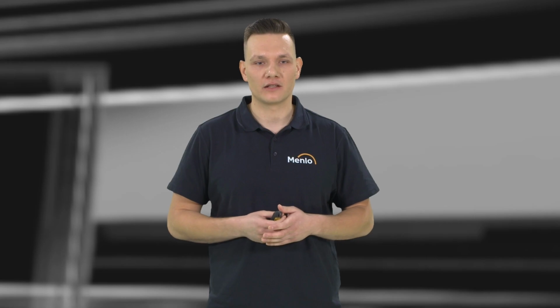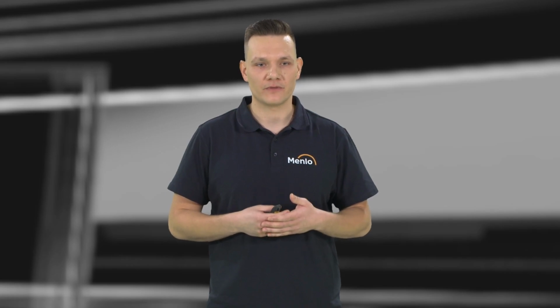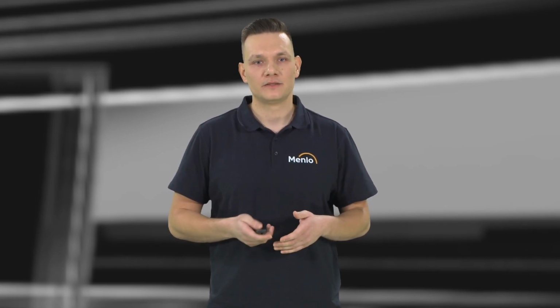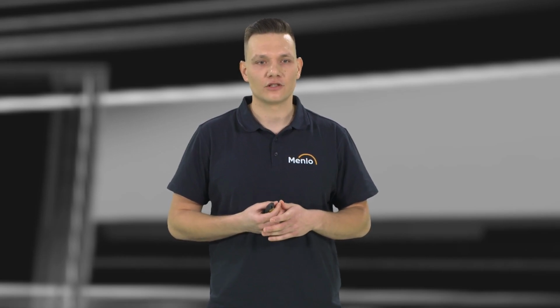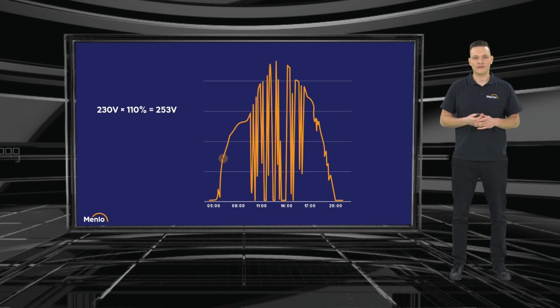Another problem we encounter is high voltage in the grid, in countries where there's too much energy and the voltage goes too high. Because of the network code, the inverter needs to shut off if the voltage is 10% higher than standard, which in this case means 253 volts. If the voltage gets too high, the inverter shuts off and waits for the grid voltage to return to normal. This translates into this kind of graph: the inverter shuts off and on depending on whether the voltage on the grid is high or low — when it's high, it shuts off.